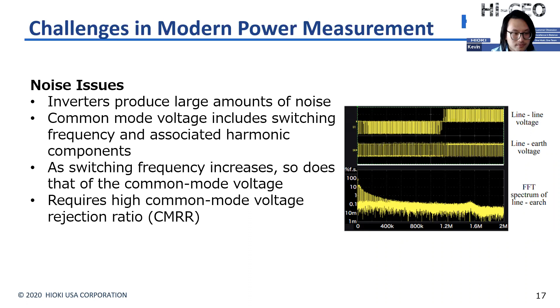So when we're measuring inverters with high capacity, we need to measure large currents on the order of several hundred amps. To counter the effects of the noise from the inverters, so we can get accurate power measurements, you can connect the power analyzer and the current sensors directly together.